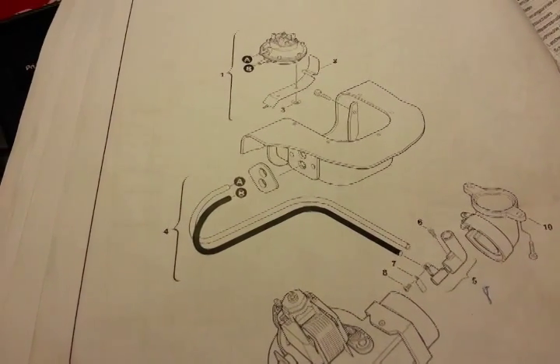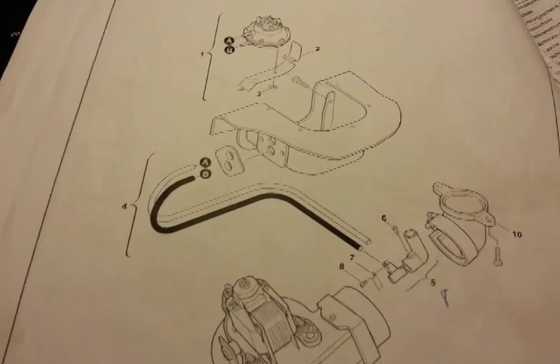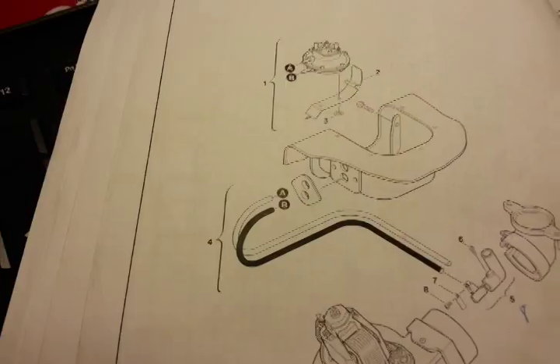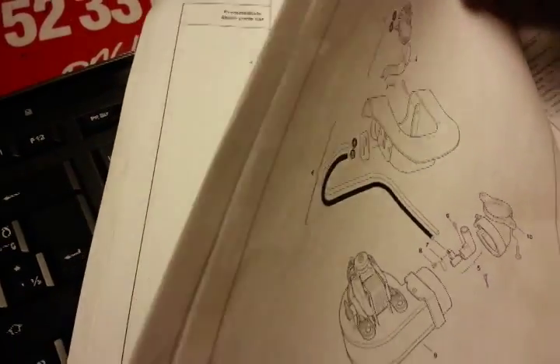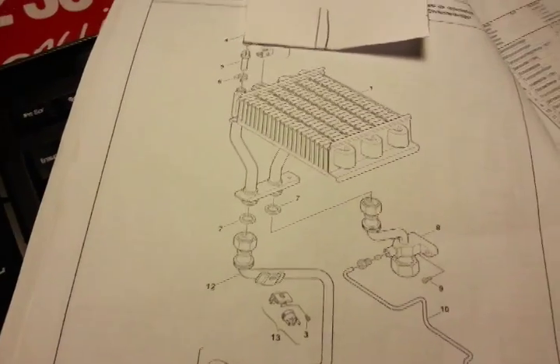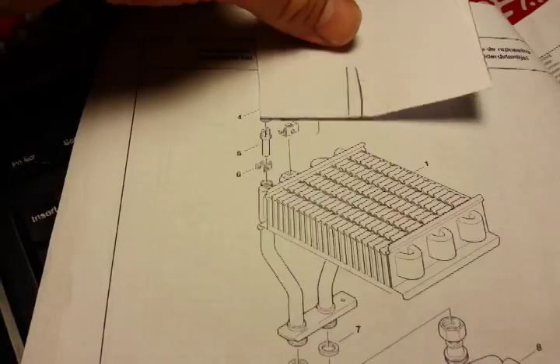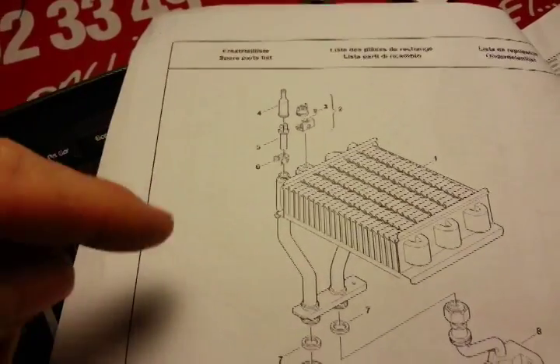If you have checked this and still got the E2 fault code, there can also be a problem with the temperature sensor that is measuring the temperature out of the heater. It is an NTC sensor sitting here.